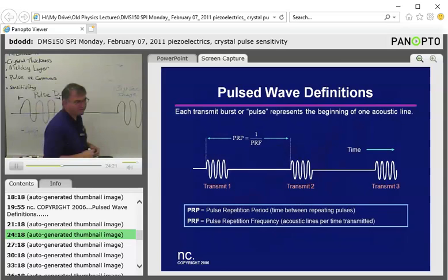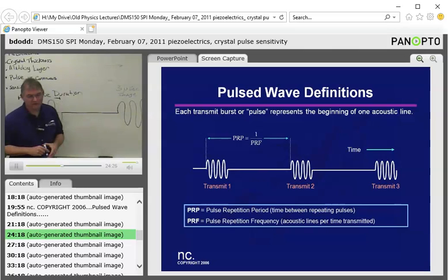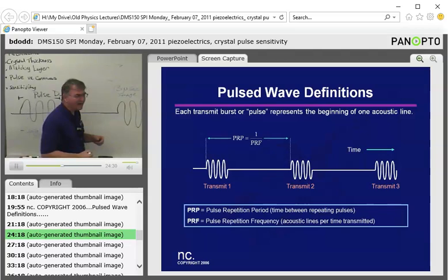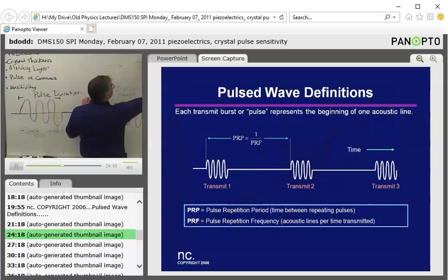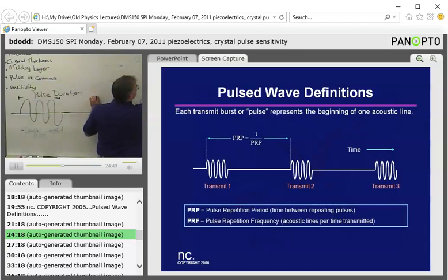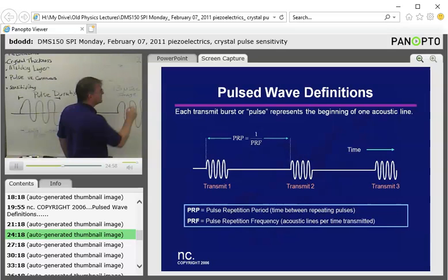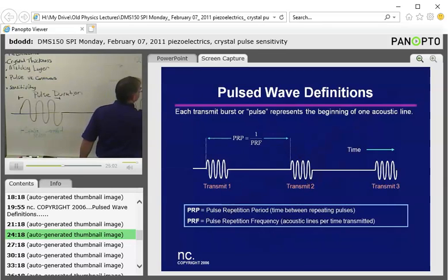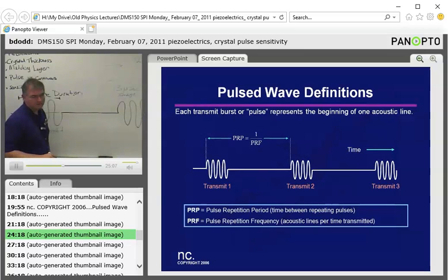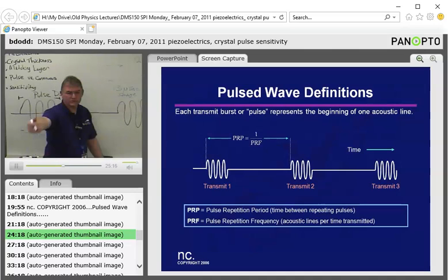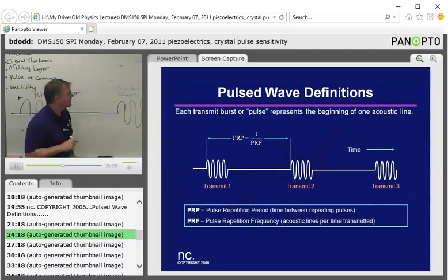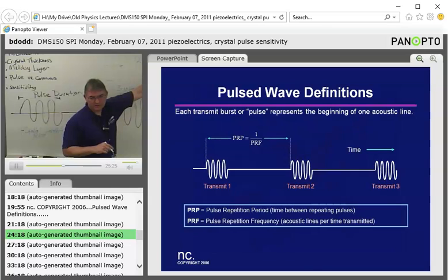So now I want to image a great big fat person who has a liver that's 20 centimeters deep. How long do I have to wait between sending out pulses? I have to wait 20 centimeters times 13 microseconds per centimeter. Okay? And how long is that? 260 microseconds, right? Or about 0.26 milliseconds. All right, so that's how long it takes just for one pulse to go 20 centimeters deep and come back. And that's how you can calculate it. Your depth times how long it takes to do a pulse.